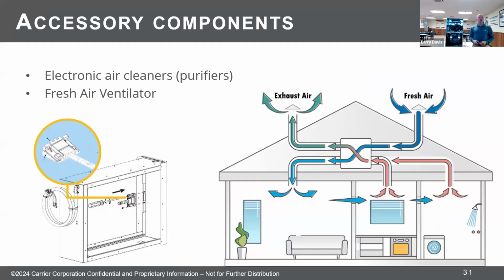One of the big changes is on electronic air cleaners. There is a chart, way at the end of the last presentation, I think, that says for a certain voltage, if it has a certain amp rating, if it's above that, then it's a potential ignition source. None of our accessories meet that threshold. However, there is a requirement that airflow has to be proven before you turn on an electronic air cleaner. So that's what you're seeing here, and you'll see it again. If you're putting in an electronic air cleaner or an air purifier, it has to have the airflow proving sensor in it. If you're putting in a fresh air ventilator, we just have to make sure that we are not recirculating air. Typically, if you install that according to its installation manual and guidelines, where you're not recirculating that air, then you should be fine.